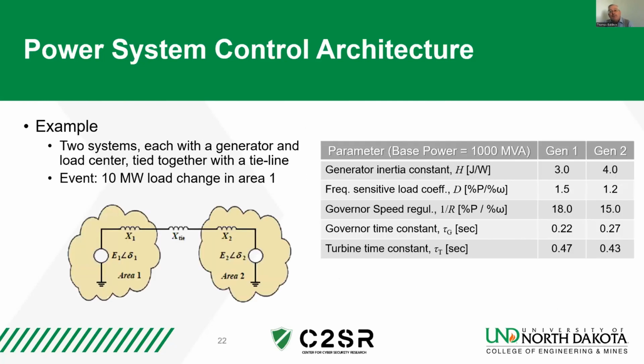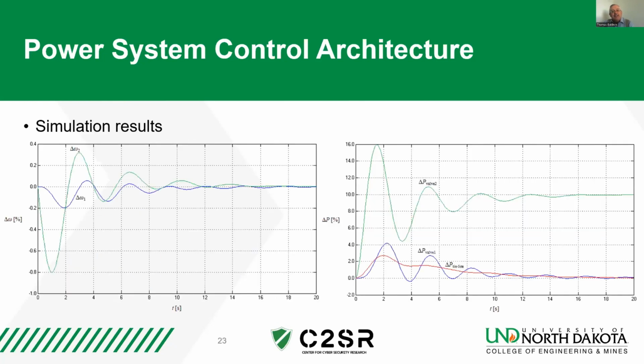Take a quick example. We have a two-generator system, we connect our two generators and two systems tied together by a tie line, and we have some generator parameters there. What happens if a 10 megawatt load change takes place in area number 1? We can then take a look at what happens to the swings in the area. We see that the onset of the load will cause a shift in power and take that power out of the rotating masses. The system senses this by changes in frequency within both areas.